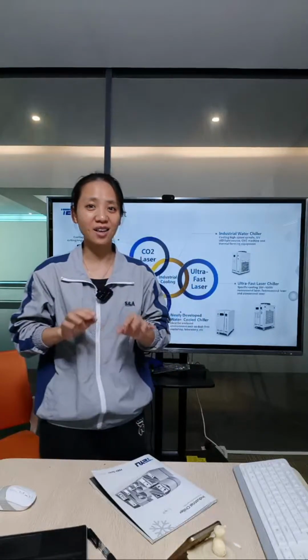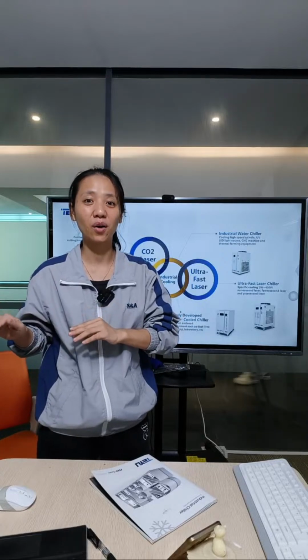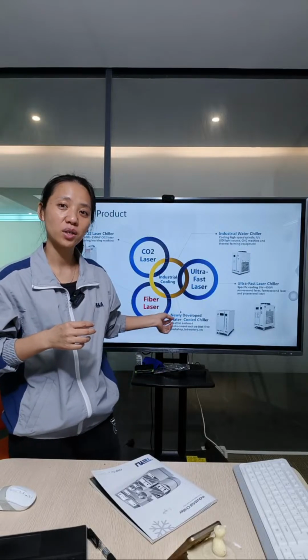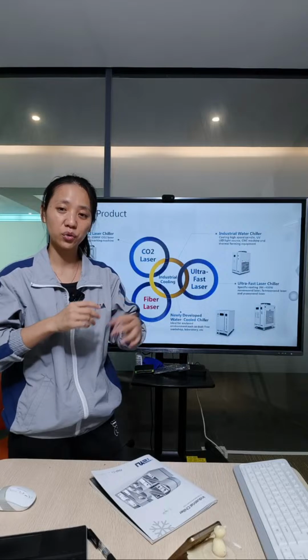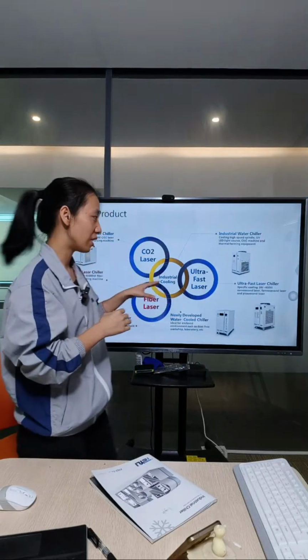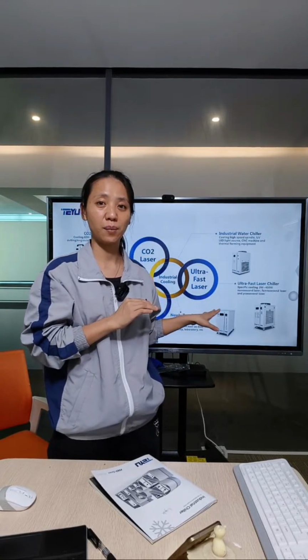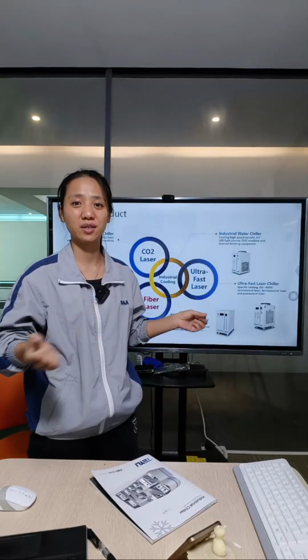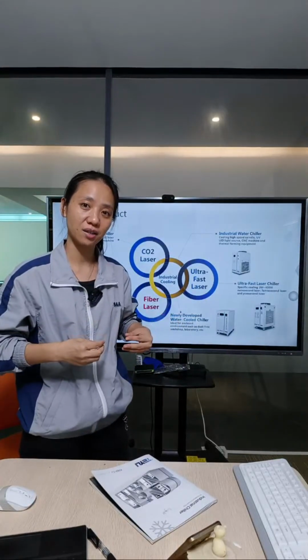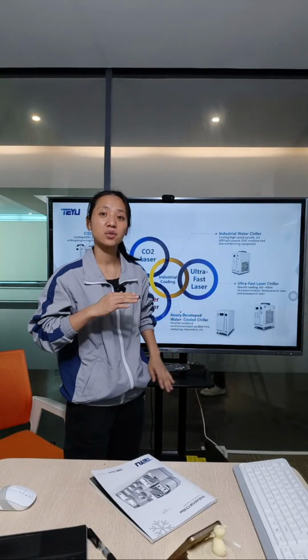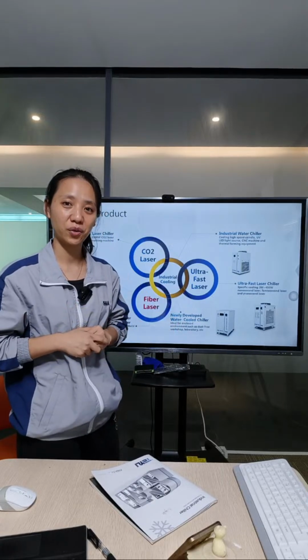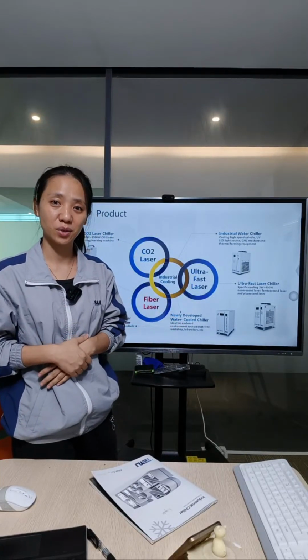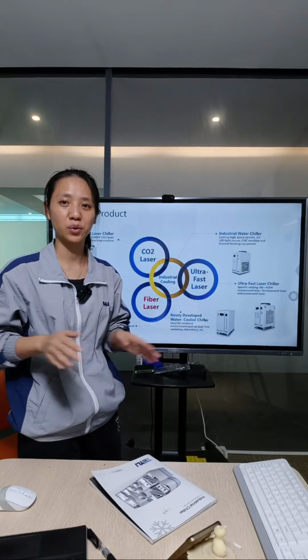As I just said, because the water-cooled water chiller doesn't have a fan inside, you must make sure there is an external cooling system in your outdoor environment, since it has no fan for heat exchange. You need to connect it to an external system, for example a cooling tower, air conditioning system, or any other outdoor cooling system. Once connected, it can work perfectly to meet your requirement of no airflow or noise in the cooling solution system for your laboratory equipment.